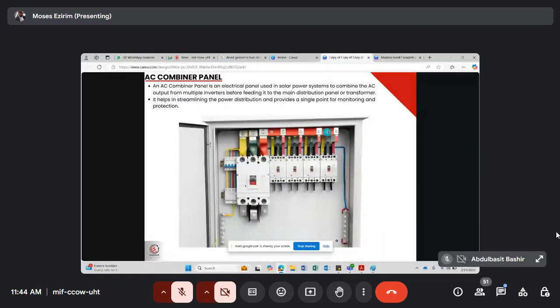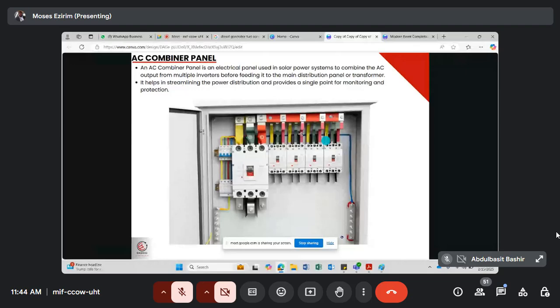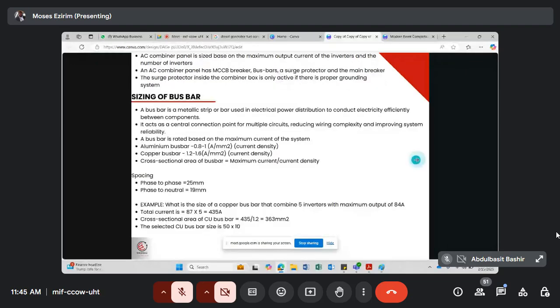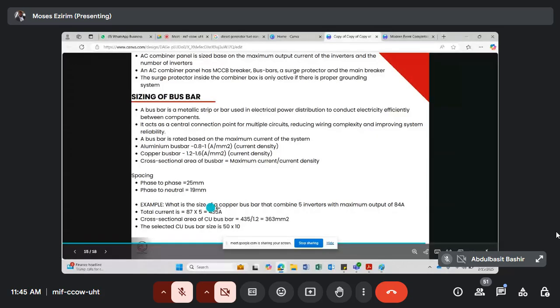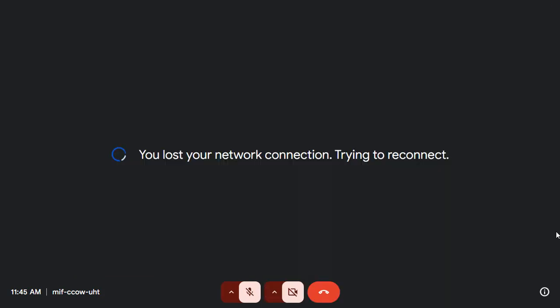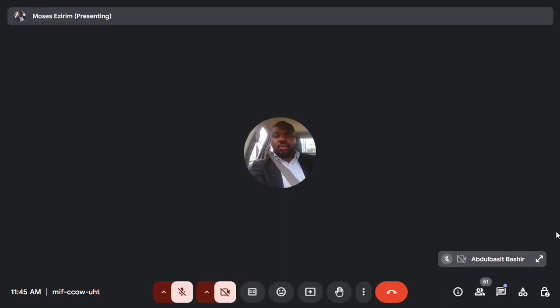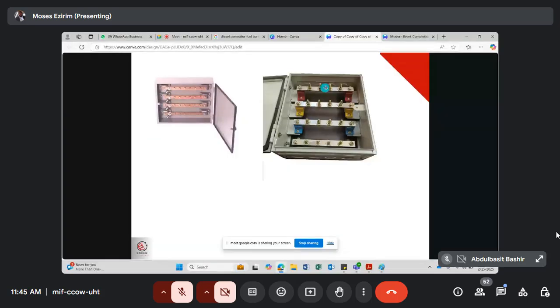Remember, there is a thickness and a width. How do you know the thickness? You know the maximum current divided by the current density. All right. So I'm using the least one, because if I can size for the least one, then it can accommodate the higher ones, all right? So for copper, between this and this, there should be a 19 mm. This is the aluminum bus bar. Know how to space it.